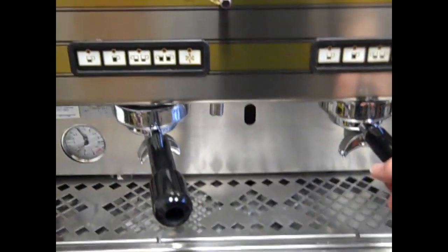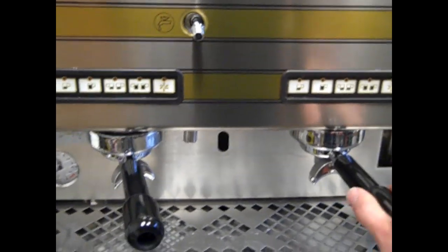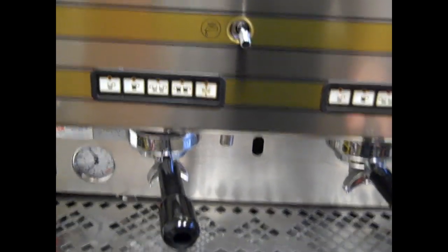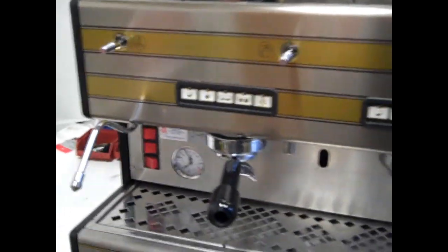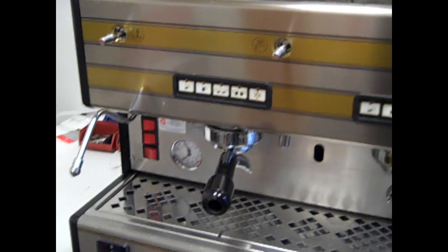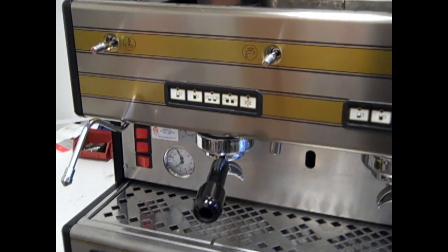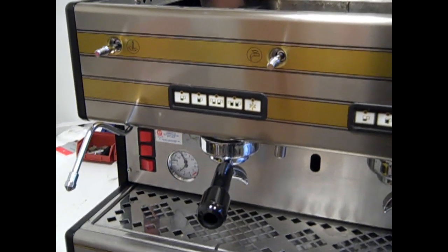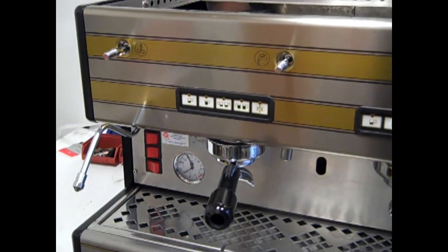Everything's operating optimally. We've calibrated this machine via the pressure stat to operate at roughly 210 degrees, which is pretty typical of La San Marcos. They tend to run a little hot and cool off over the years, which is good for the customer because it ensures a pretty long, high-temperature cycle for a machine like this.